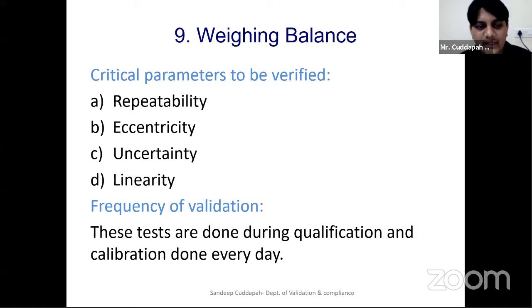In case of repeatability, you give the same weight at the same place and verify whether it gives the same result repeatedly or not. In case of eccentricity, you place the same weight in different locations on the balance and verify the eccentricity. Even uncertainty, so how much percentage variability is there, that you will verify in the uncertainty.